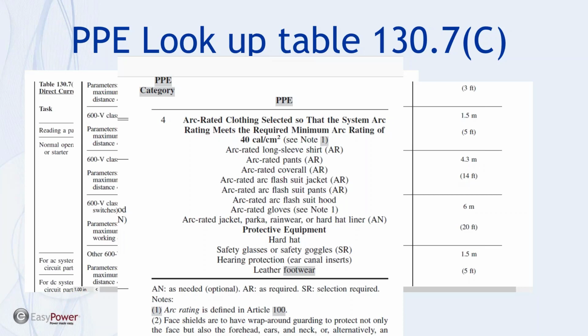So what's the bottom line? Even if the business owner does not want to pay for an arc flash study, even work on his system to be de-energized would require us to put on PPE rated for 40 calories just to be able to test the voltage on the switchgear to make sure the voltage has been removed. Well, you might say, Jim, if we know the energy will be less if we work on something farther down the line on the one-line diagram. Well, my next question might be, how accurate is this one-line diagram if he really hasn't done an arc flash study? So let's set that aside for a second.